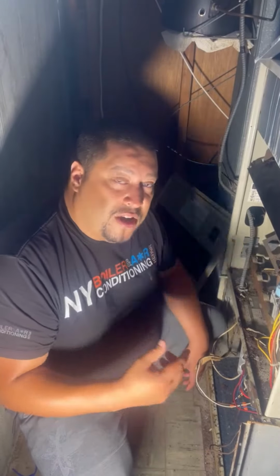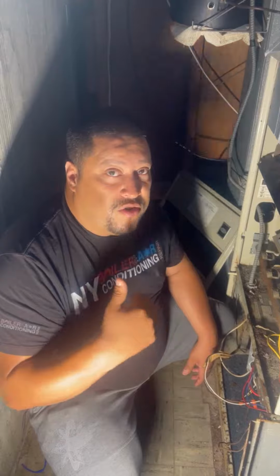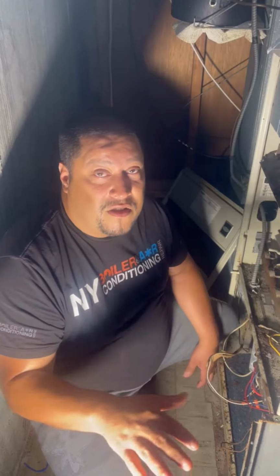I come over here, make sure we have 24 volts, which I do. I make sure we have power going to the board, which we do, but we have no power coming out. So that already automatically tells me the board is already bad.